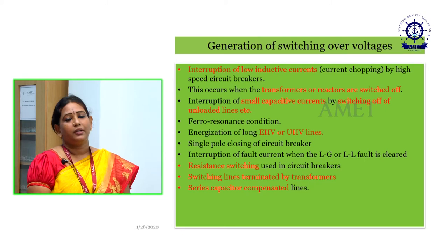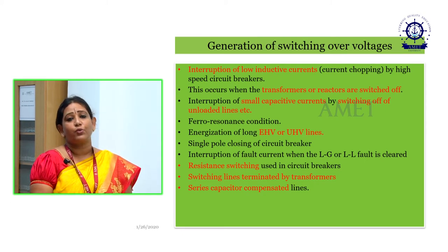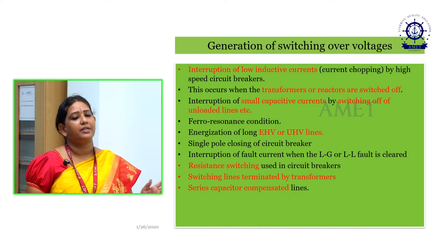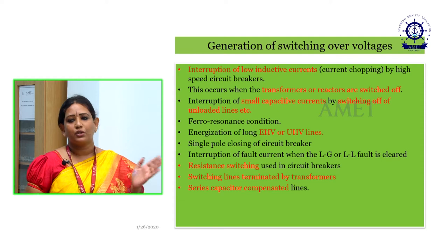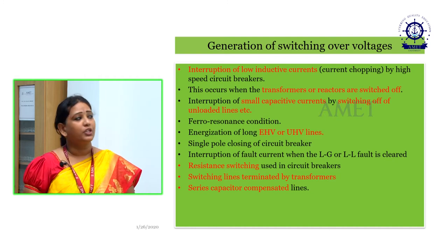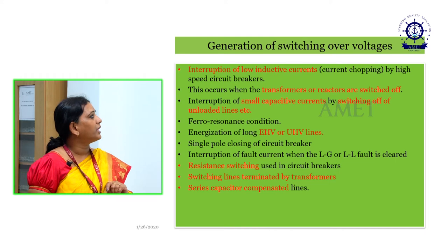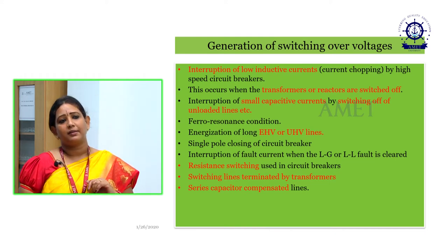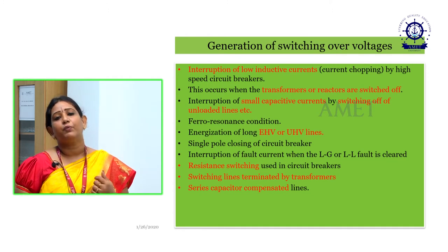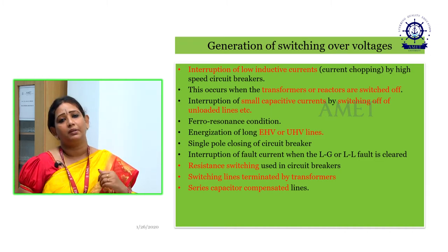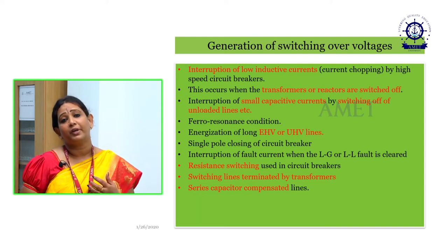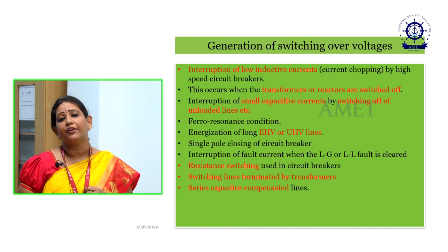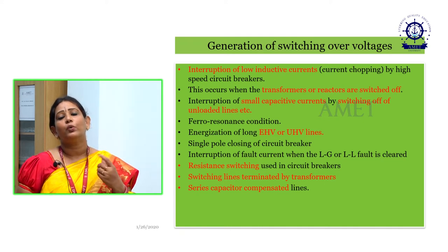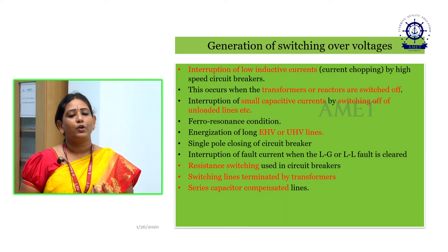As I said before, the generation of switching over voltages has many causes and does not depend upon a single reason, because our entire power system is a very big network, from generation to the distribution side. Many operations are performed by power system engineers. So we'll see. The first one is the interruption of low inductive currents, because as engineers we forcibly interrupt the current, say a low inductive current. Interruption of low current by high speed circuit breakers is a challenging task, and it creates a deionizing effect in the power system, which in turn leads to over voltage generation, which we call a switching over voltage.